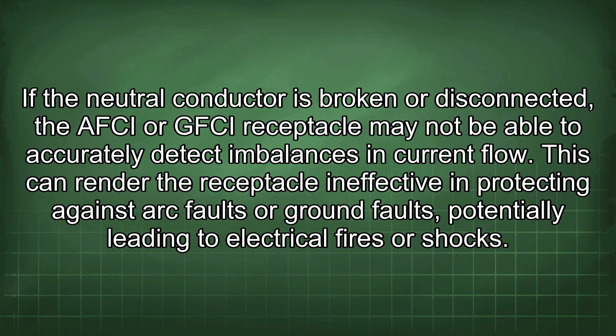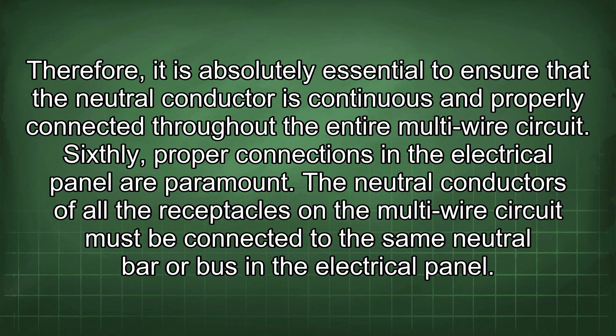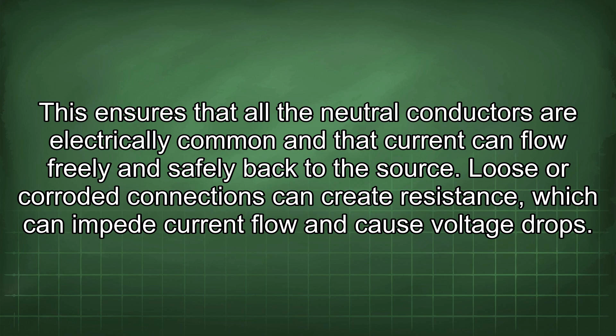Sixthly, proper connections in the electrical panel are paramount. The neutral conductors of all the receptacles on the multi-wire circuit must be connected to the same neutral bar or bus in the electrical panel. This ensures that all the neutral conductors are electrically common and that current can flow freely and safely back to the source. Loose or corroded connections can create resistance, which can impede current flow and cause voltage drops. This, in turn, can affect the performance of the AFCI and GFCI receptacles and potentially lead to nuisance tripping or failure to operate when needed.